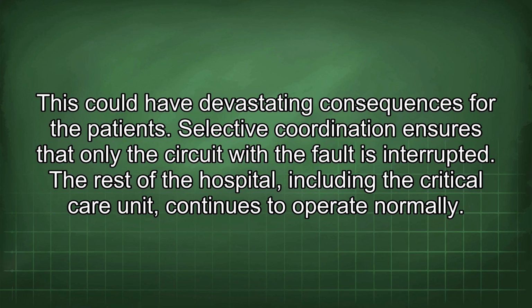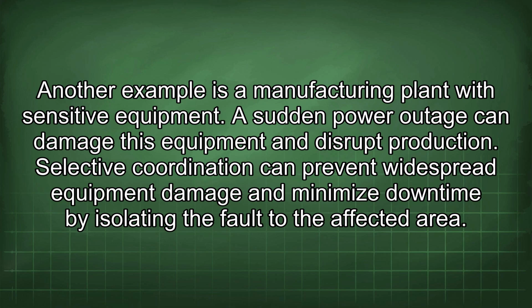Selective coordination ensures that only the circuit with the fault is interrupted. The rest of the hospital, including the critical care unit, continues to operate normally. Another example is a manufacturing plant with sensitive equipment. A sudden power outage can damage this equipment and disrupt production. Selective coordination can prevent widespread equipment damage and minimize downtime by isolating the fault to the affected area.